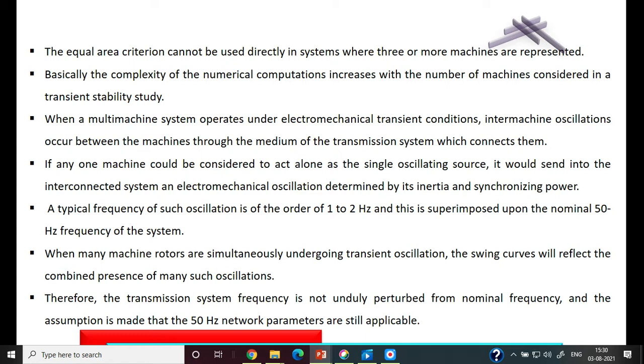If any one machine is considered to act as a single oscillating source, and a disturbance occurs in that machine, it would send into the interconnected system an electro-mechanical oscillation determined by its inertia and synchronizing power. Even a disturbance in a single machine propagates to the other machines through the interconnected system. The typical frequency of such oscillations is in the order of 1 to 2 Hz, superimposed on the normal frequency of 50 Hz.